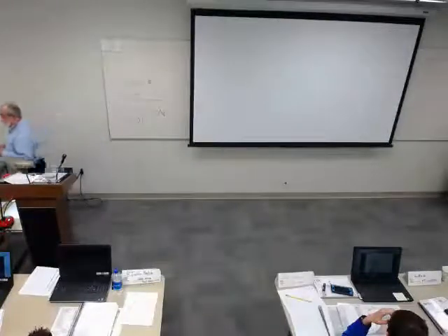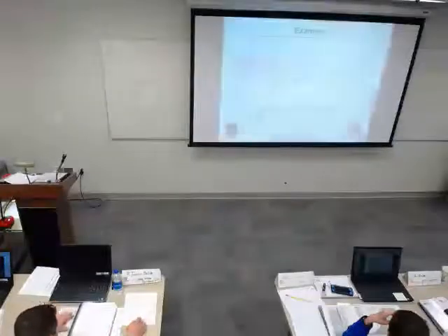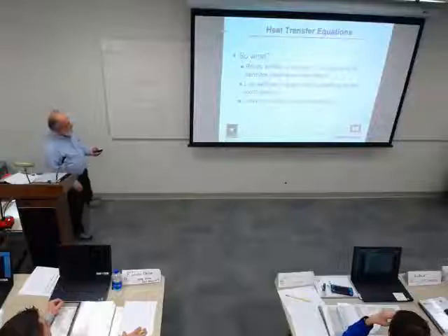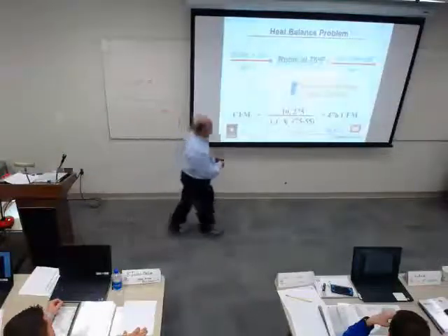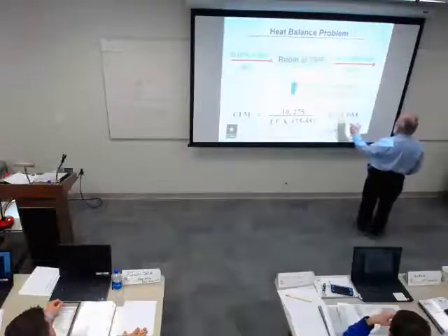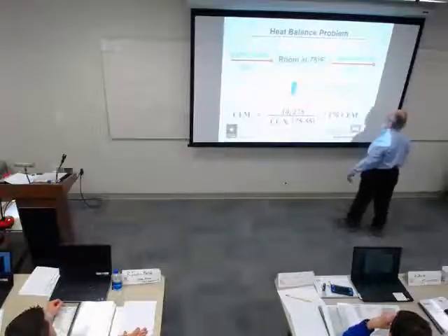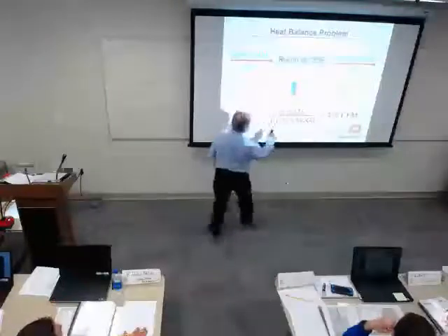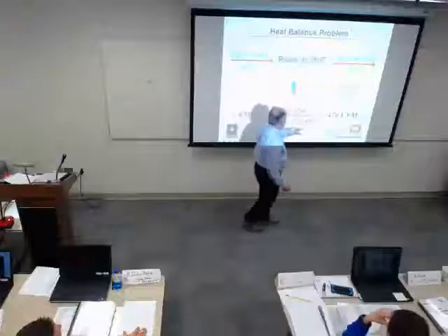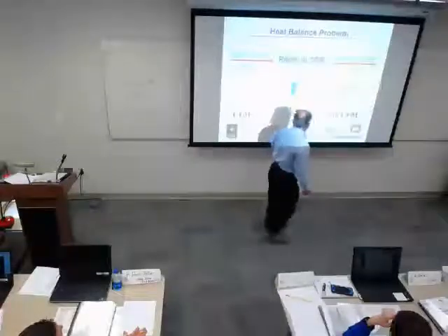So what they did is they took that equation and messed around with it. And right here, this is the 10,275 that we got from the slide before. Here's the change in temperature. Here's that factor, that F thing. We multiply it times that, and that's going to give us the CFM.